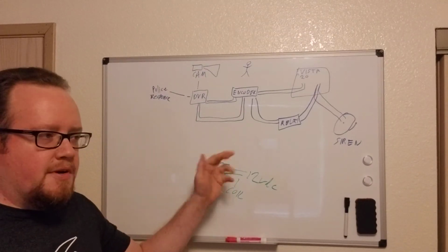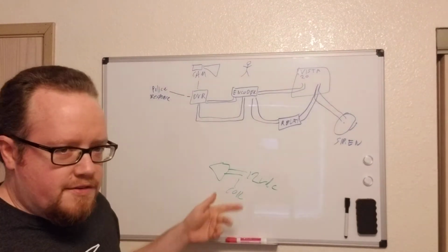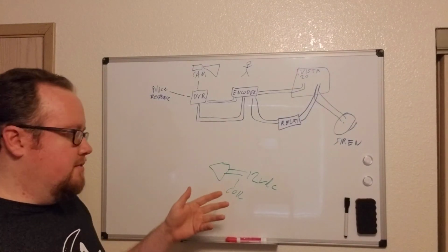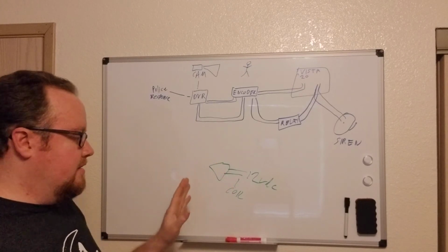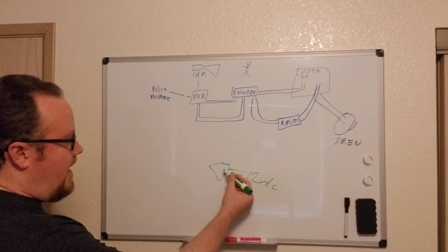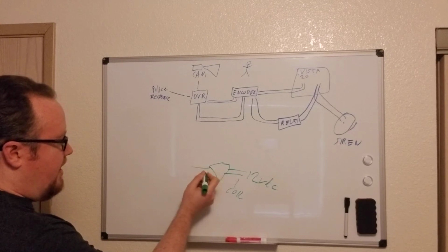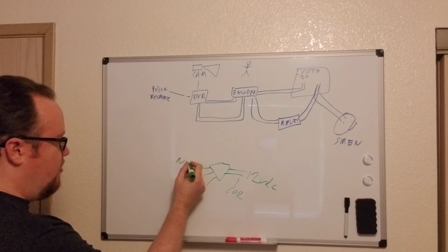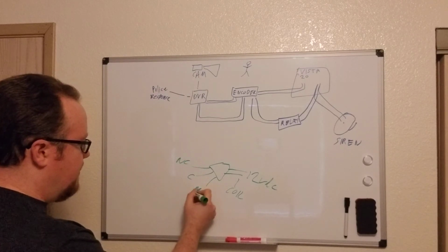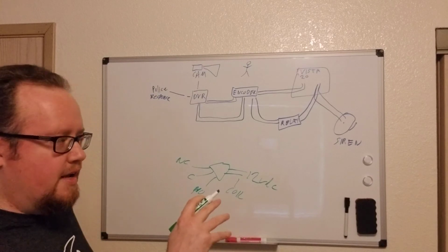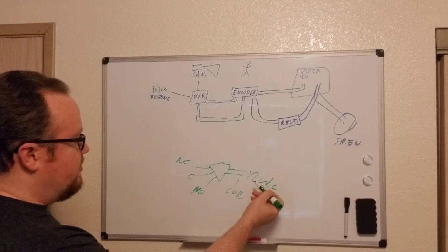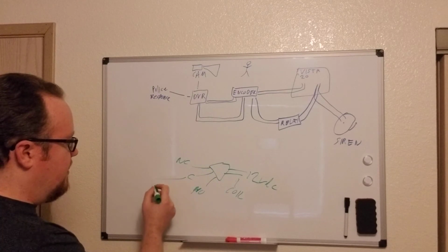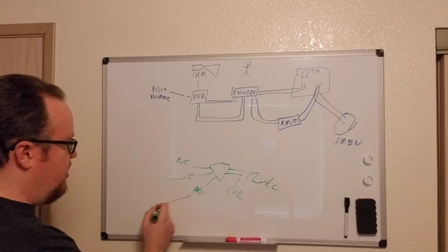These relays can be tripped on 120 volts AC, 12 volt DC, 24 volt DC, any combination of those. They're made in all different styles. So the voltage simply activates the relay, and here you have, say, 3 wires: a common, normally open, normally closed. So, pardon my horrible writing, I'm not a drawing expert. So when the voltage is applied, these switch. So you have a wire going somewhere, and then you have a wire on normally open.